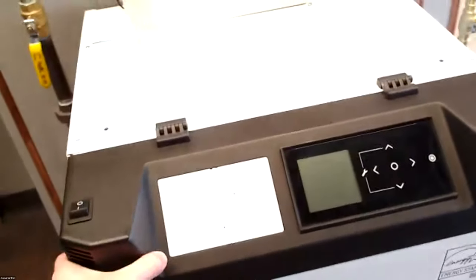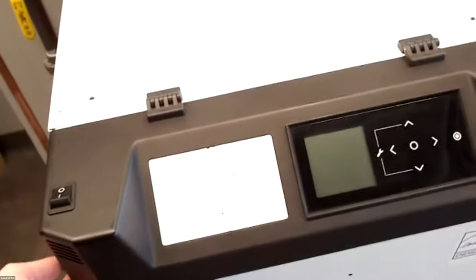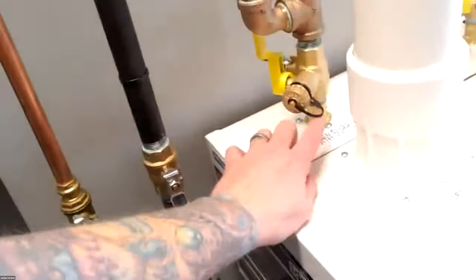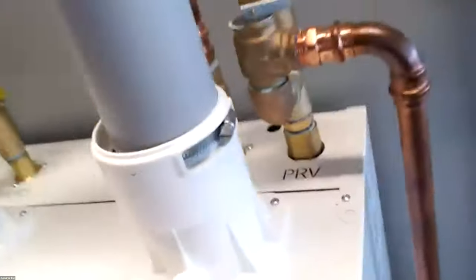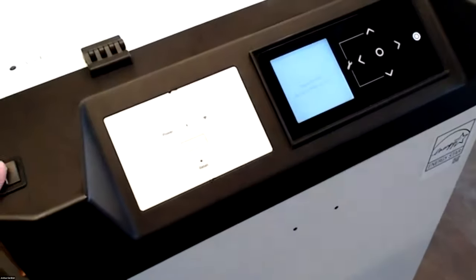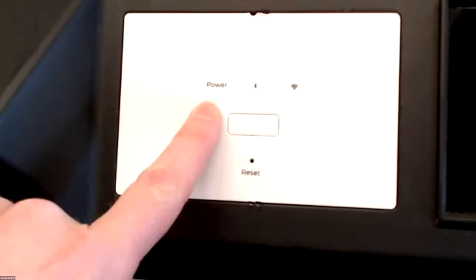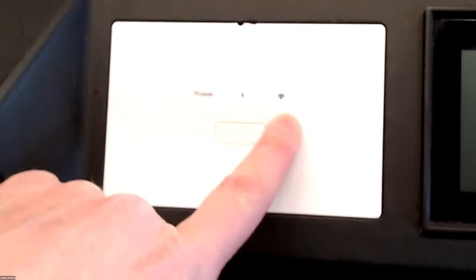I think more or less it's for shipping, just to keep this control nice and snug. So you'll have those two. So just note, trying to open this up, you got those screws in there. This cover will not lift up if those screws are still in there. For domestic connections, they're labeled supply, inlet, and the pressure reducing valve back here. On the front control of this boiler, we actually have a power switch. We have that Wi-Fi control that's right in here. Real simple: power, Bluetooth, Wi-Fi, and then a reset, and then your main button.